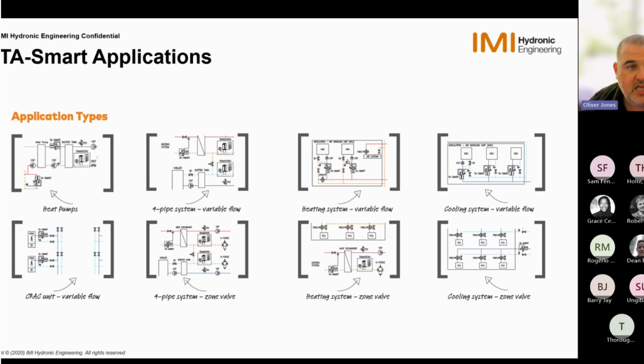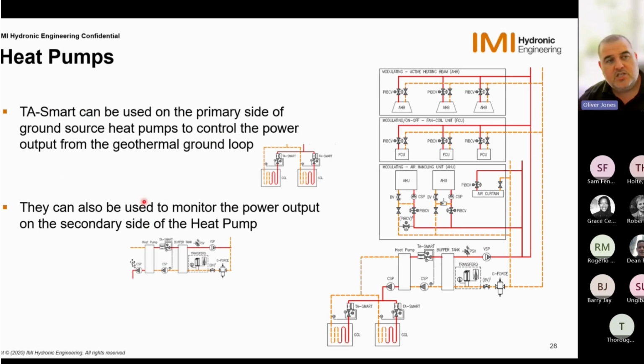So, applications. Typically, we wanted to show some applications of where these valves are going to be installed and how they're intended to be used. So from a heat pump point of view, the TA Smart can be used on the primary side of the ground source heat pumps to control the power output from the geothermal loop. So we can see both of those here. And we can also monitor the power output on the secondary side of the heat pump itself. So obviously with the temperature probe on the return and our internal on the flow, plus our flow position, we can stipulate how much power output we want from that secondary side, or certainly monitor.